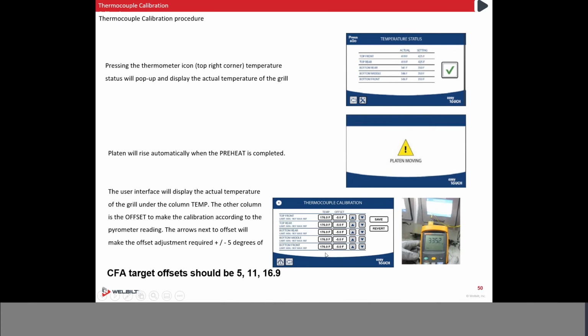So you're going to match your temperature, and then you're going to do the offset to one of these that's the closest to it. So if I'm going 335 and I'm temping it, or 380, let's say 381, and I get to 15 of an offset, I'm going to go ahead and take it to 16.9 at that point. Same thing with if it's close to 11, just take it to 11. Basically what that will do is it'll cause the unit to heat a little bit more. So the temperature is a little bit higher than what it actually is. So those are your offsets.